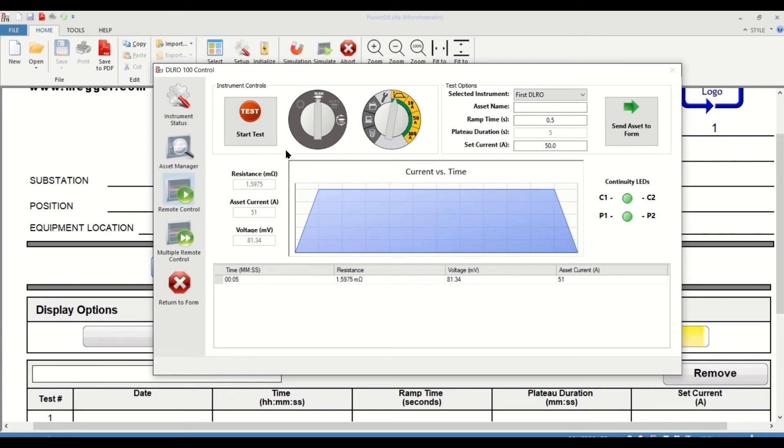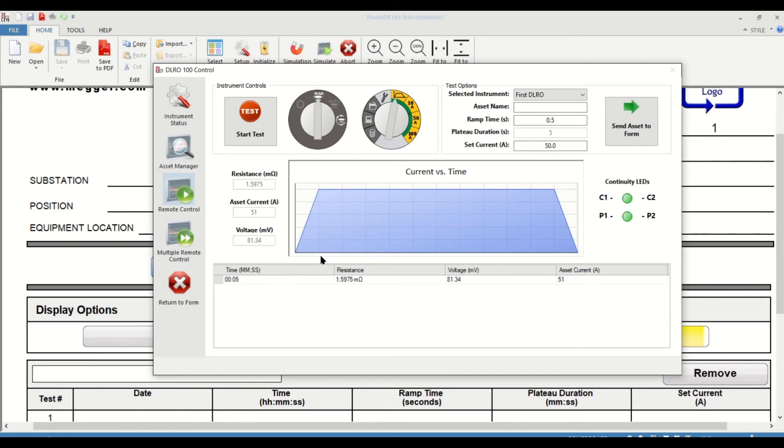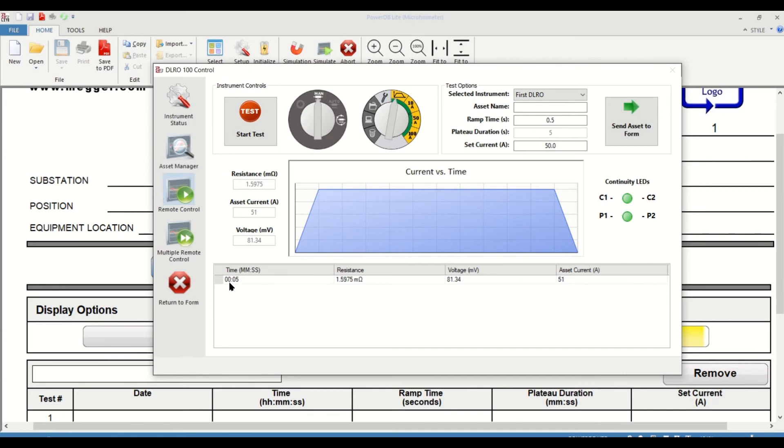You can see that a resistance of 1.5975 milliohms was measured after injecting 51 amps and after a voltage drop of 81.34 millivolts was encountered across the test object. You can see the ramp that's representative of a 0.5 second ramp. Then you can see a 5 second plateau and then a 0.5 second ramp back to zero. This magnitude would be about 50 amps. You can see that the plateau duration and the time matches, and the resistance value is documented here with the voltage and the current.